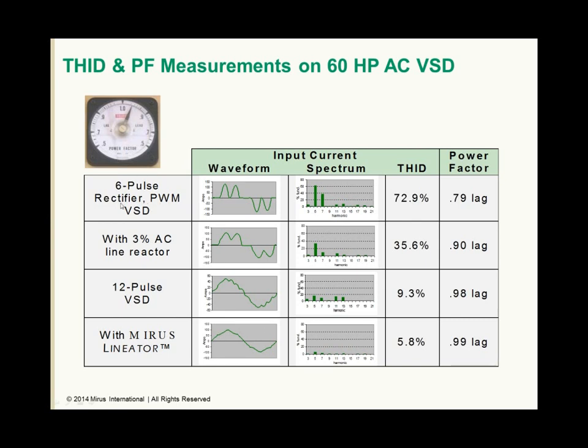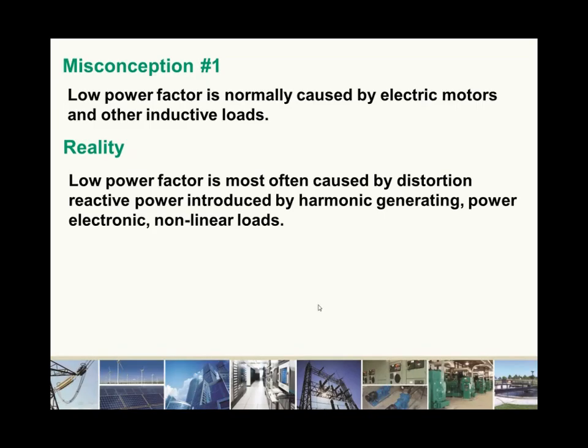The 6-pulse variable speed drive shown here, in combination with a passive harmonic filter that we offer, the Lineator, will result in very sinusoidal current and very low harmonic content. Here we have 5.8% current distortion and essentially a unity power factor. Typically with power electronic loads, the displacement power factor will be near unity. The true power factor can be quite low, though, due to the distortion harmonic component. So if we remove the harmonics, we will restore the power factor to near unity.